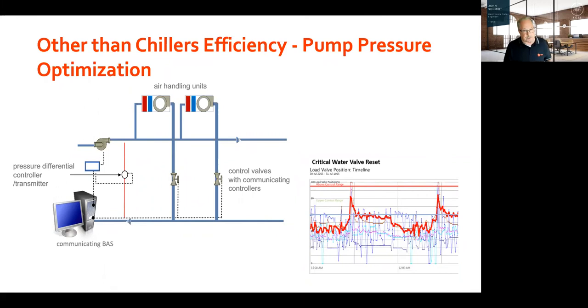So this is kind of a picture of that, an example of the air handling units and the coil that might be bad, or piping was undersized, or an area grew and required more chilled water. The graph at the right is an analytic that we run on a lot of our plants, that the bold red line is really the average of every chilled water valve in the whole hospital, okay? So you can see there's a blue line, and it looks like a maroon line that's going above that solid red line. So this kind of pinpoints, all right, these are the air handlers, coils or valves, or possibly some piping that is keeping us from slowing down the pump. We're having to pump all that pump energy just to satisfy a couple of odd air handlers that are driving that pump to run at full speed.